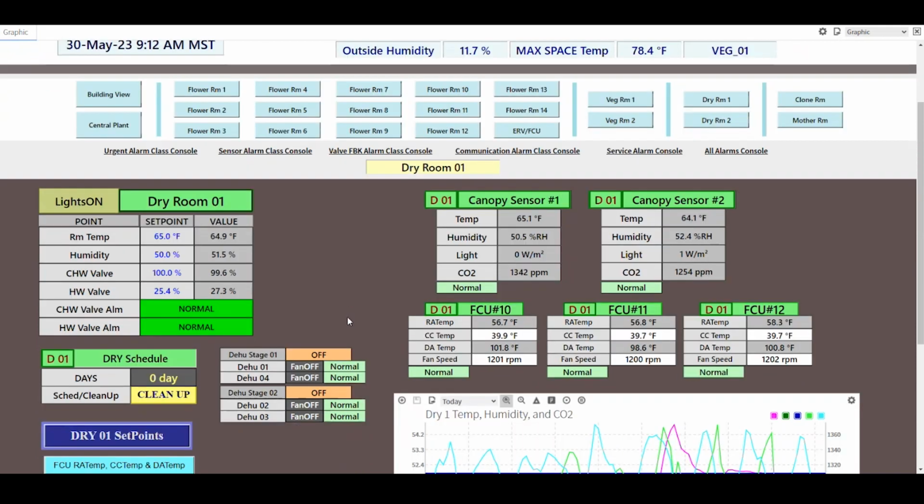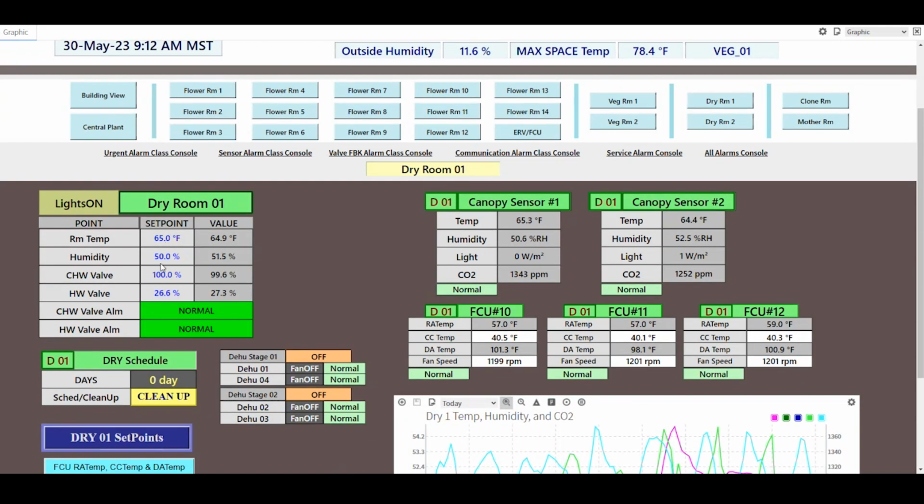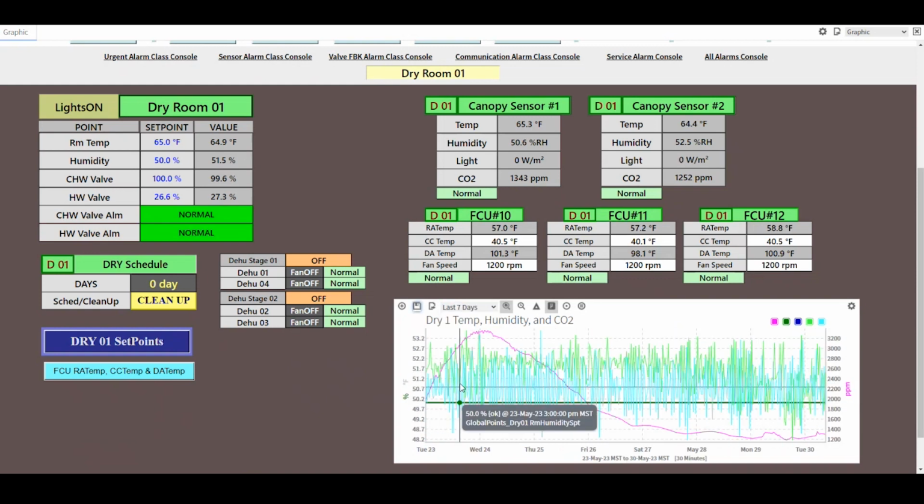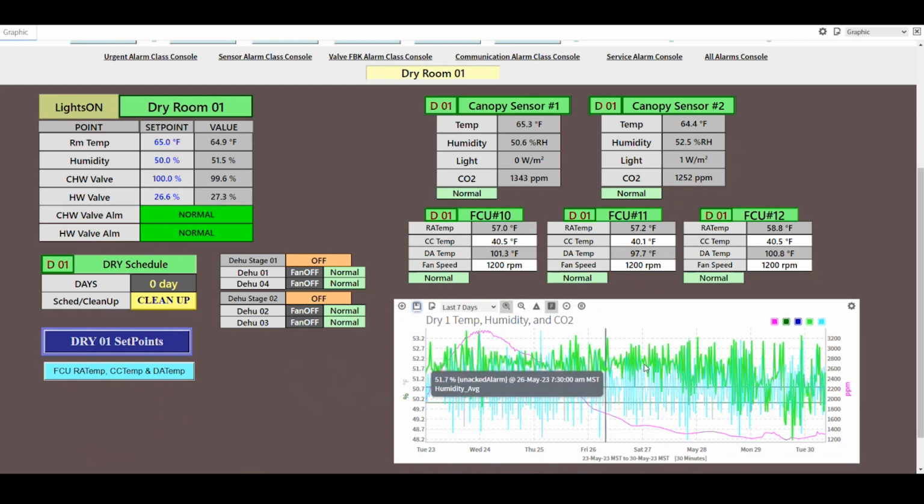So this is a dry room and it's set at 65 degrees and 50% humidity. You can see we're achieving really close to that right now. And then right now this is set to the last day. I'm going to set it to the last 7 days just to give a better sense of how the room is performing.